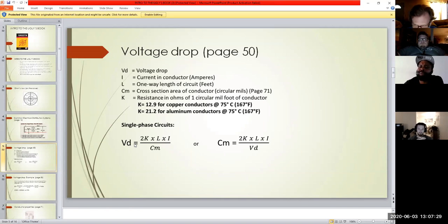Even in HVAC, you're running wire from the service panel to wherever you end up putting your unit, so you have to figure that length—say I'm running 200 feet, is this size wire going to work for me? If the voltage falls too low, it won't work because you won't have the right voltage for your unit.